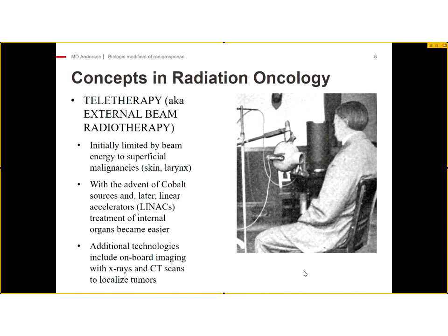then moving forward beyond that is the linear accelerator. What is a linear accelerator? The linac, they call it in the business. Basically, you accelerate electrons into a tungsten target, and on the other side, you get photons. You don't have a radioactive source, per se, you just fundamentally plug into the wall. The good part about that is, number one, the nuclear regulatory commission is not really an issue because you don't have this radioactive piece of cobalt. And number two, you have a much greater degree of control in regards to how you can modulate what you're shooting.